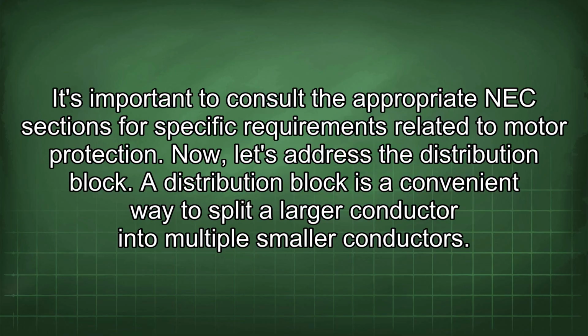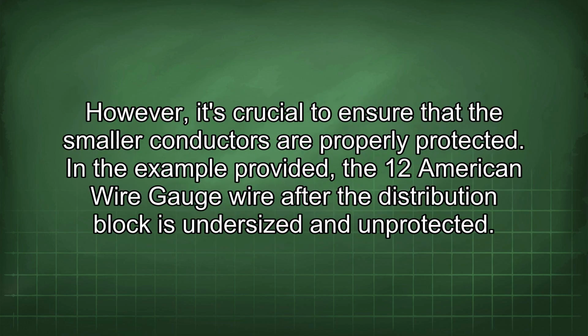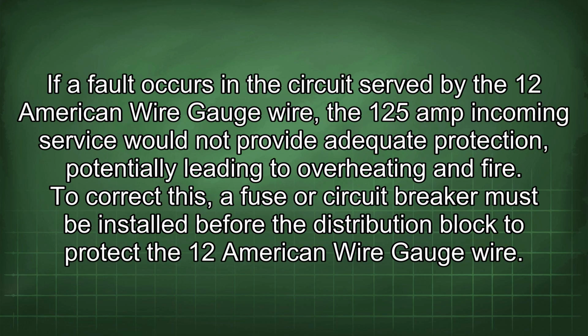Now, let's address the distribution block. A distribution block is a convenient way to split a larger conductor into multiple smaller conductors. However, it's crucial to ensure that the smaller conductors are properly protected. In the example provided, the 12 American wire gauge wire after the distribution block is undersized and unprotected. If a fault occurs in the circuit served by the 12 American wire gauge wire, the 125 amp incoming service would not provide adequate protection, potentially leading to overheating and fire.